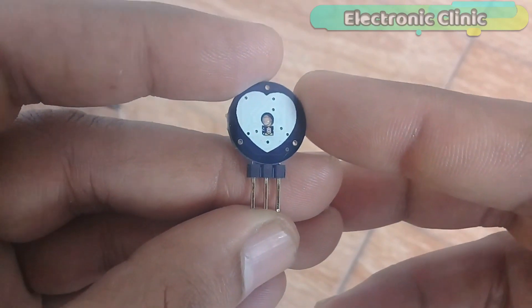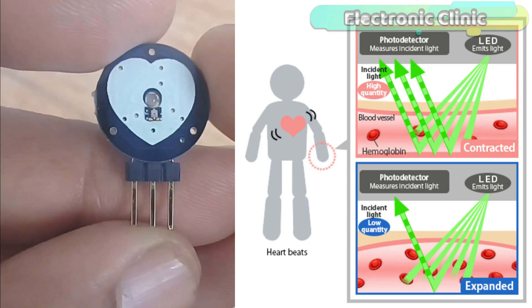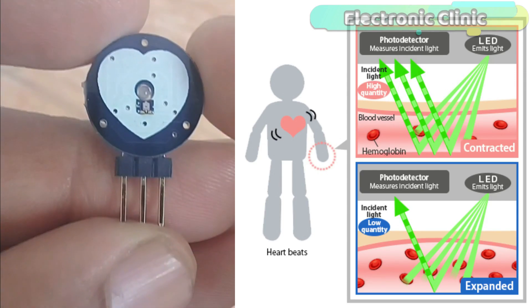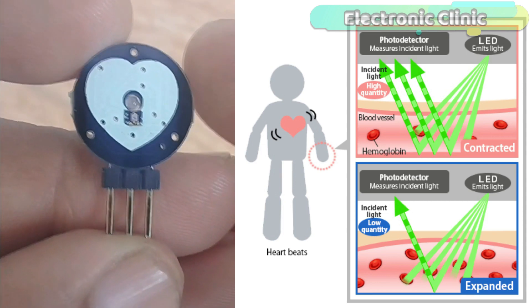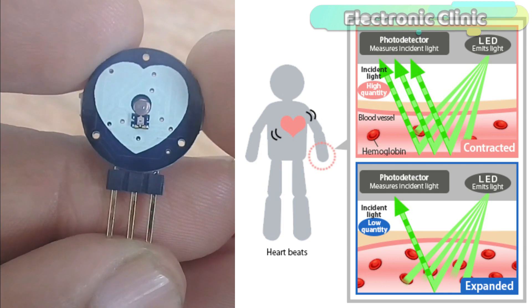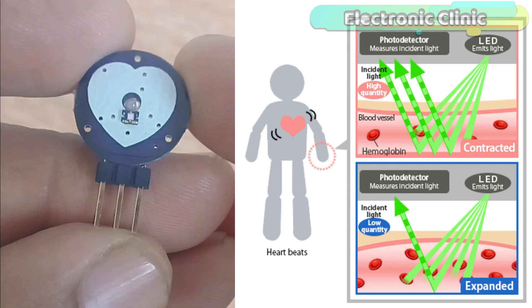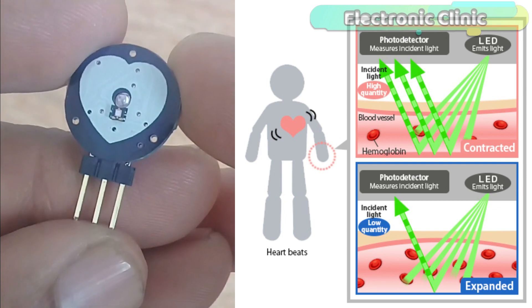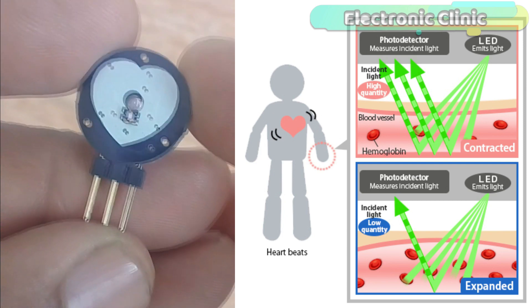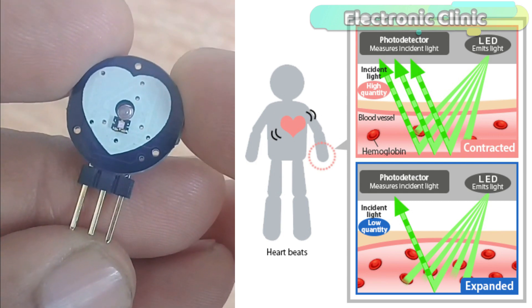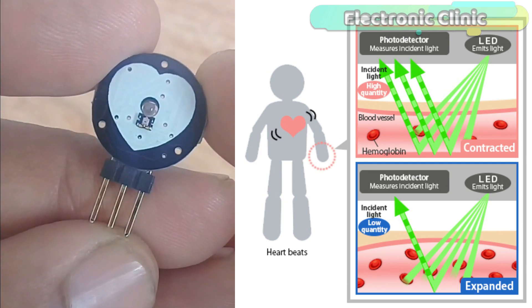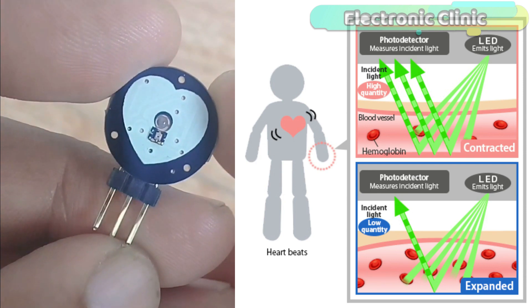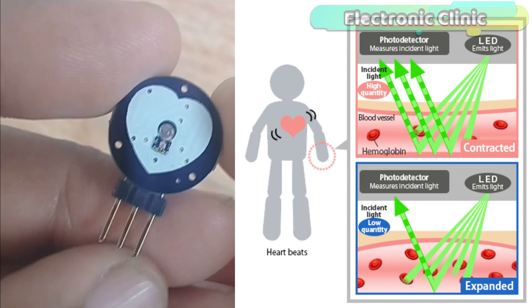This sensor module is provided with transmitter and receiver LEDs. The light-absorbing property of the hemoglobin is used in the measurement of heart rate. Light from a green LED on the underside of the monitor is shown on blood vessels just under the skin. The light that is not absorbed but reflected back is captured by a photo detector. The photo detector produces an electrical signal when light strikes it. This analog signal is converted into a digital signal, and slight changes of this signal are used to measure the heart rate.